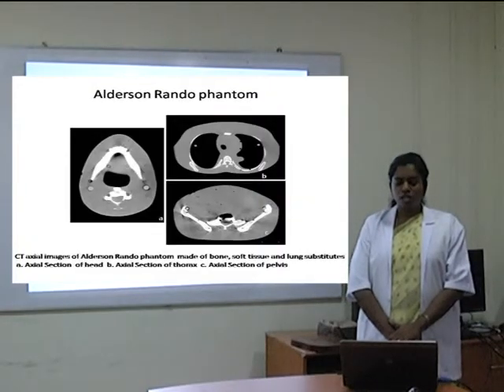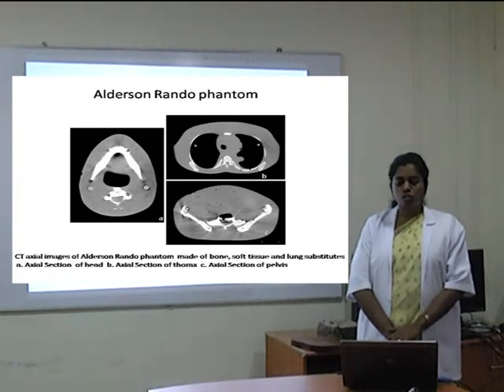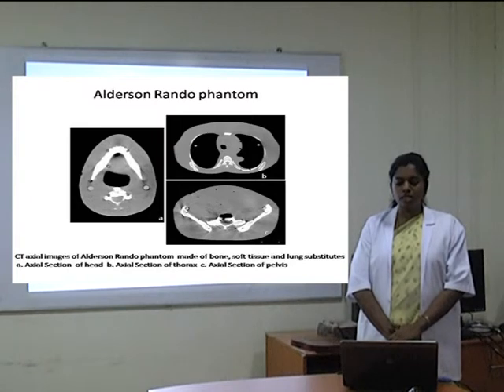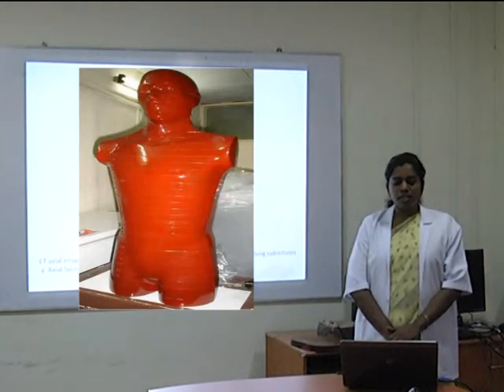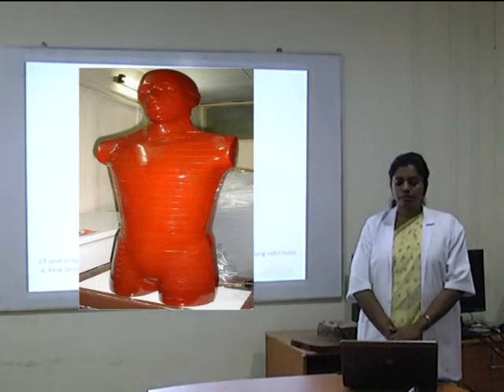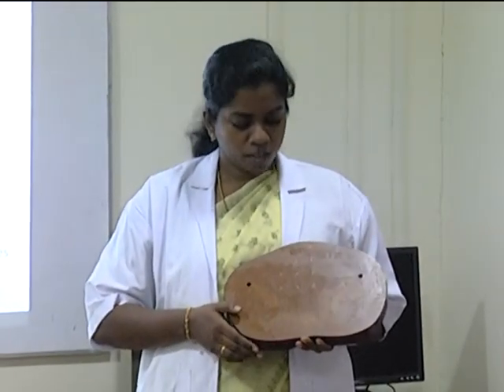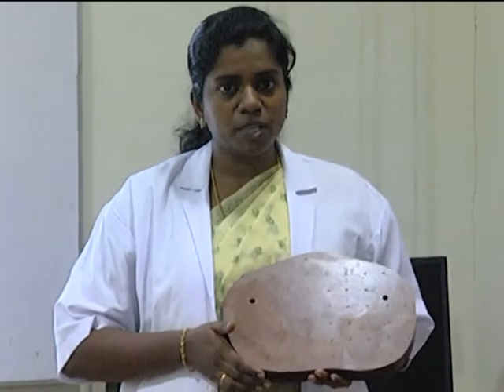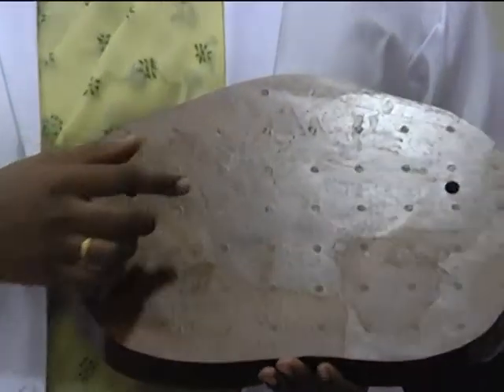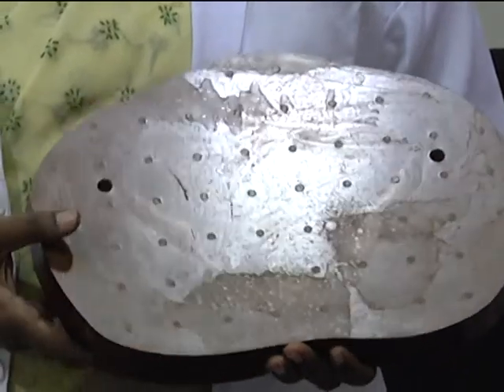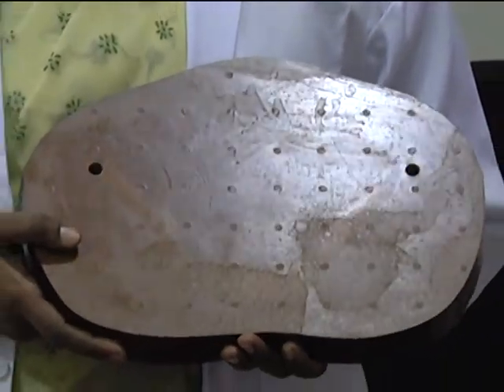Phantoms are structures made of one or more tissue substitutes used to simulate radiation interactions in the human body. For example, the Alderson Rando Phantom is currently widely used for radiation dosimetry. This is a section of the Alderson Rando Phantom, which shows that it is made of bone, soft tissue, and lung substitutes, but it has no organs in it.